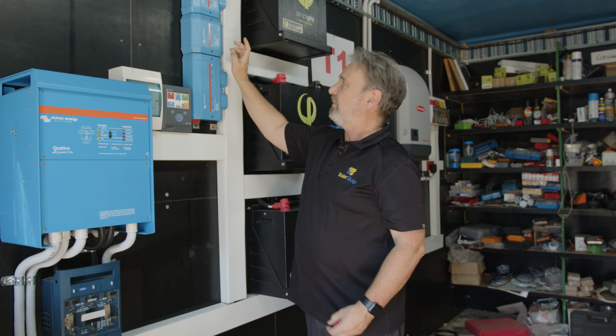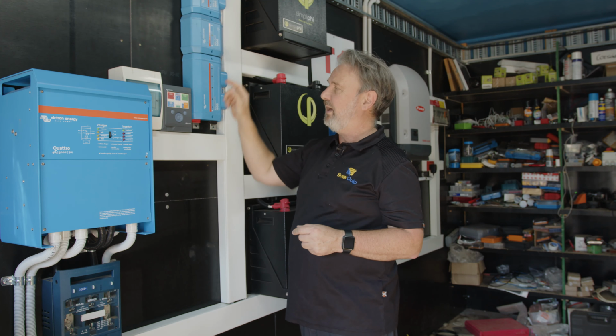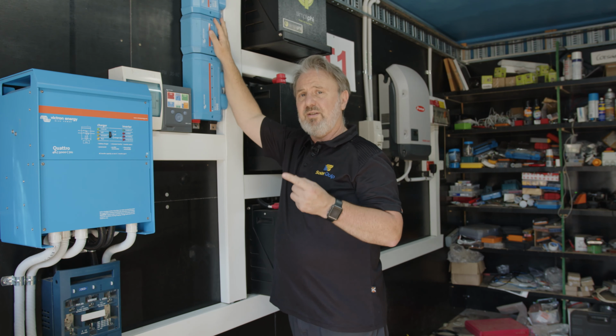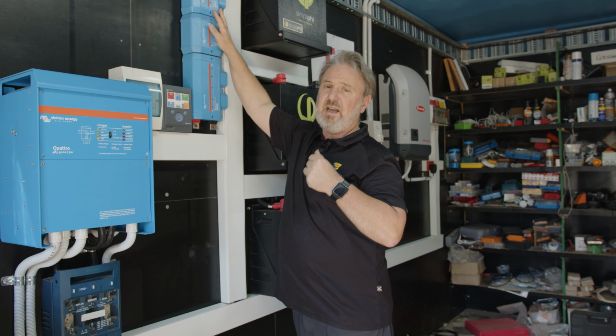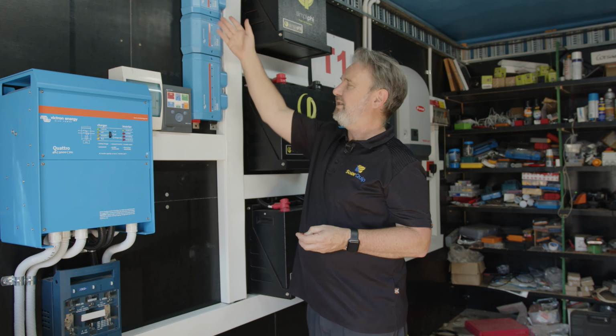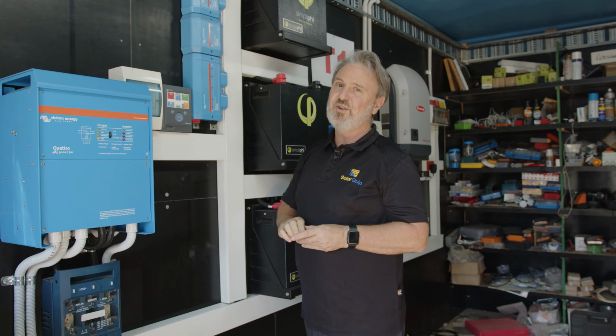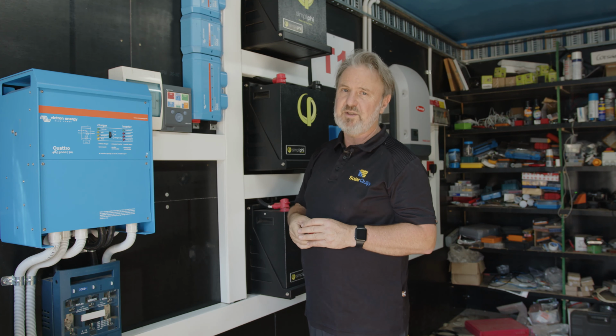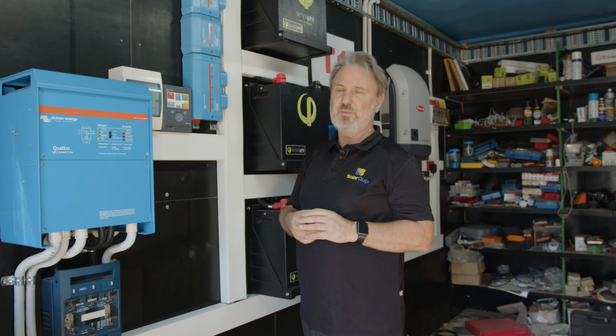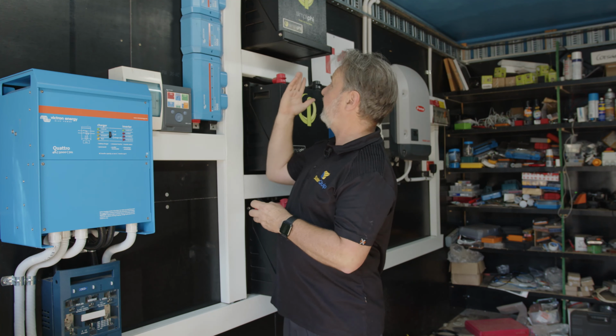So that's really nice. The Lynx Shunt is a 1,000 amp smart shunt. It converts from DC or analog to digital and transmits the information to the Color Control or other GX devices so that you can see the amount of energy flow between the batteries and all sources of generation and load. The distributor is where you connect inverters and other generation sources on the DC side, like our wind turbine. And so it's sitting up here, and it too can be plugged together. So this system is very cost effective. If you were to build a bus bar system like this, you'd probably spend more than just buying this beautiful unit. And it can even have integrated fusing built in, so monitored fuses, which is a really nice feature, because it's a requirement of our new battery standard, AS/NZS 5139, to have string overcurrent protection in a parallel battery system. We have more than one battery string in parallel. So there you go. This is the AC and DC coupled Victron Fronius and SimpliPhi system here at the lab.